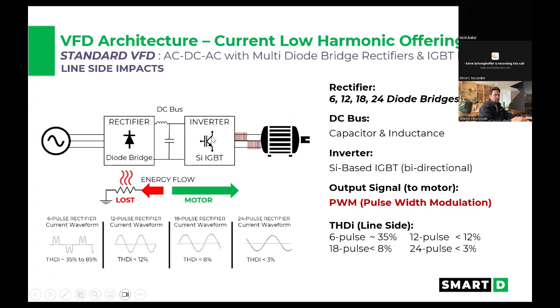The active front end came along, and that's where they took, if I just go back here, they took this rectifier bridge and they took everything on the back and put it on the front. And now you've got a back-to-back drive. So this is what an active front end is. So the front end is active. It's constantly monitoring the harmonics and what's coming in, just like an active filter, but now it's inside of the drive. But it's still IGBT based. So there are still some challenges with that because IGBTs have been around for about 40 years. And even though we keep increasing their ability to handle heat and things like that, you're still going to have to deal with a square wave signal. And you now have to introduce some very large mitigation on the front end as well.